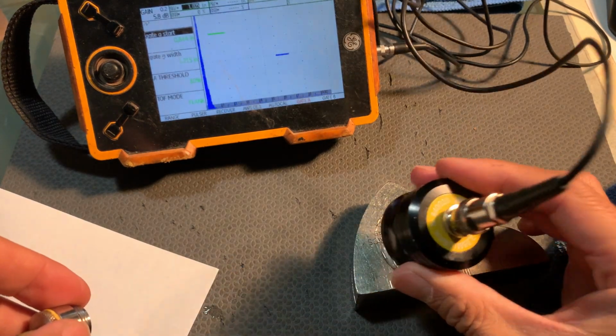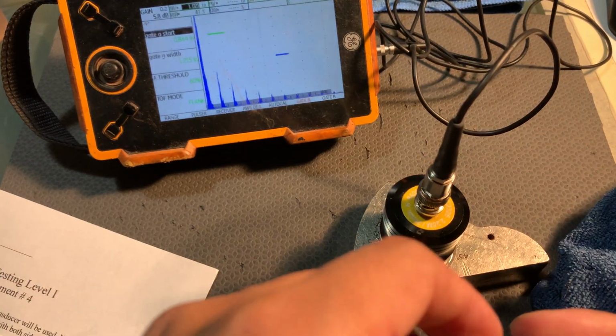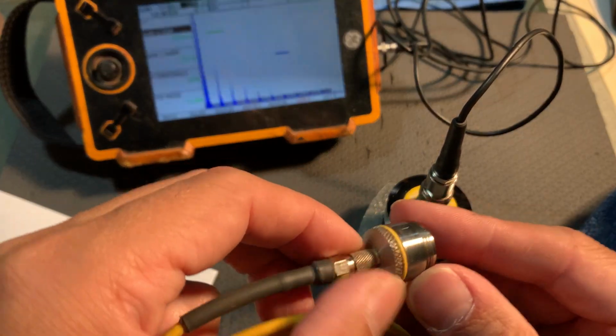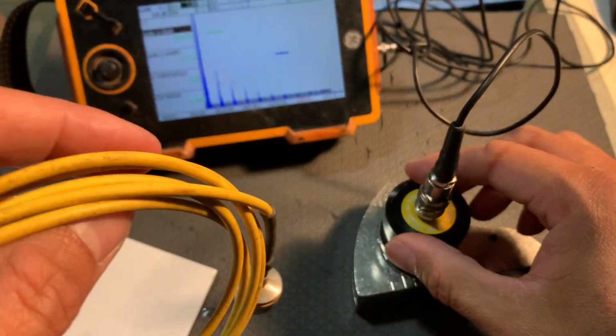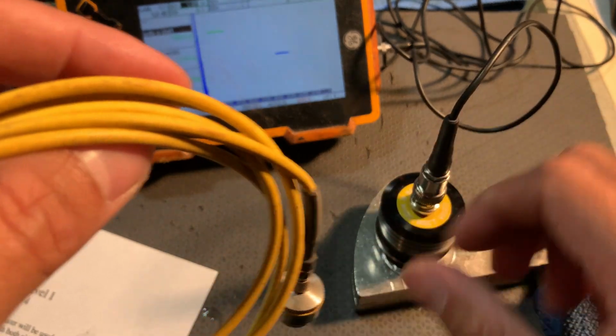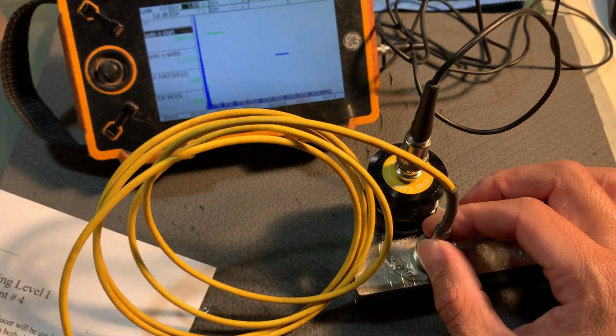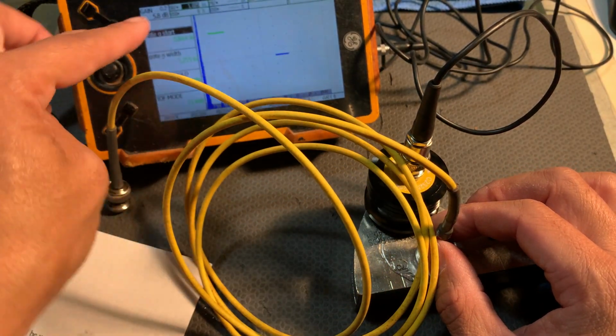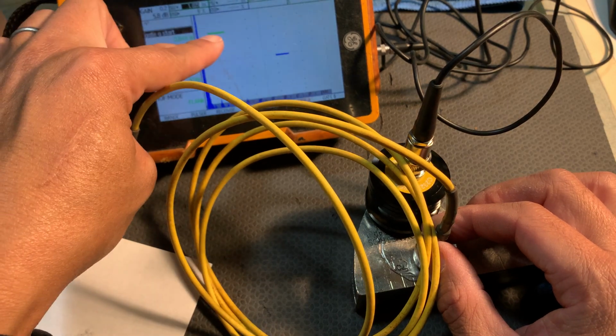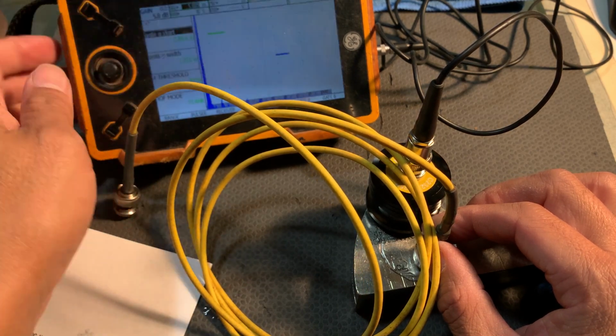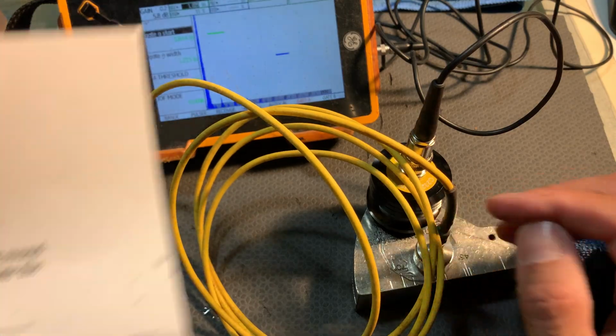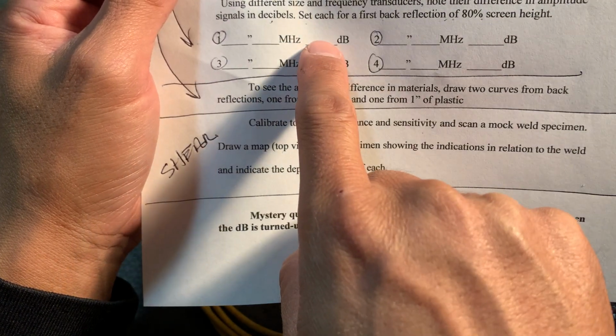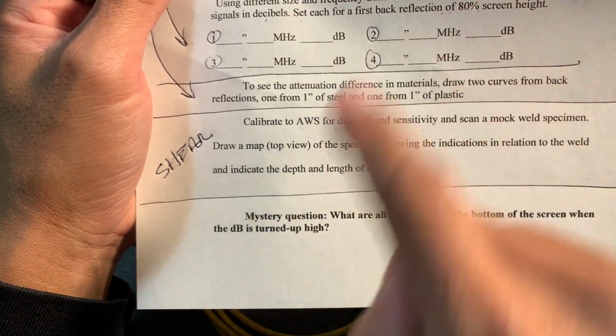This one I have here is, I believe, a 2.25. This is probably a 3.0. What you do is switch it out for this one. Of course, plug it in, and then turn it up until you get 80% screen height. As far as turning up your decibels, record your decibels per each transducer on here. So you record the megahertz of the transducer you're using, and how many decibels it took to get your 80% screen height.